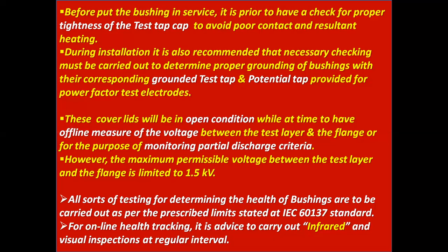All sorts of testing for determining the health of bushings are to be carried out as per the prescribed limits stated in the IEC 60137 standard. For online health tracking, it is advised to carry out infrared and visual inspections at regular intervals.